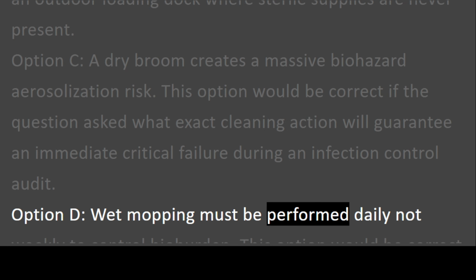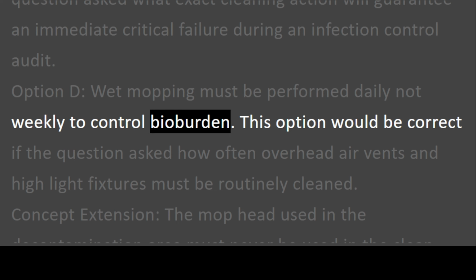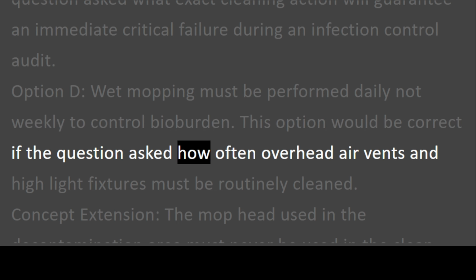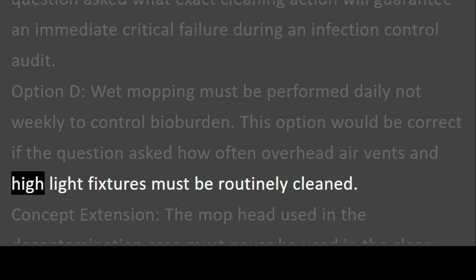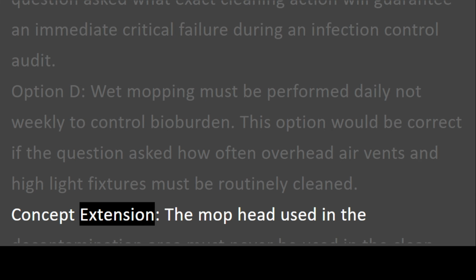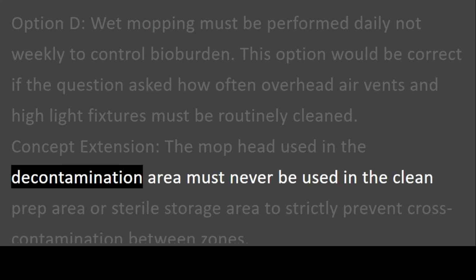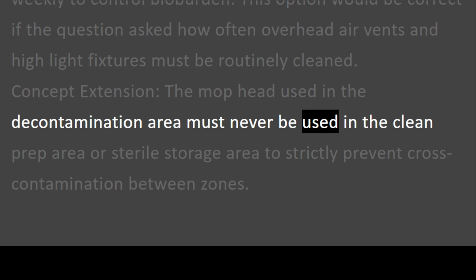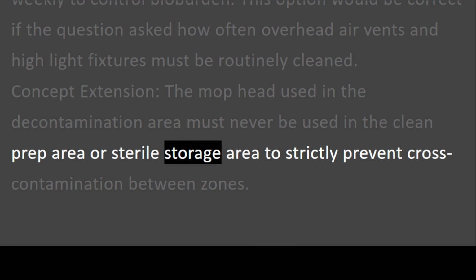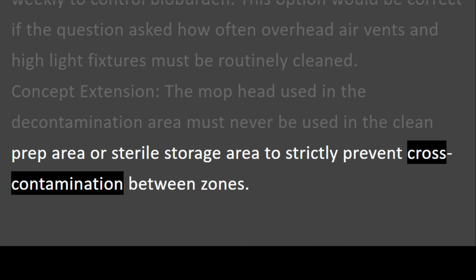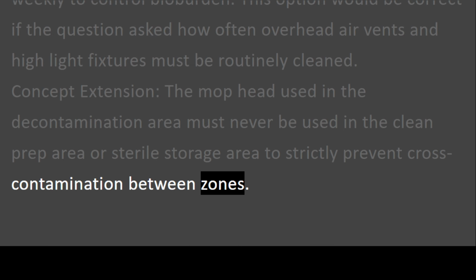Option D. Wet mopping must be performed daily, not weekly, to control bioburden. This option would be correct if the question asked how often overhead air vents and high light fixtures must be routinely cleaned. Concept extension. The mop head used in the decontamination area must never be used in the clean prep area or sterile storage area to strictly prevent cross-contamination between zones.